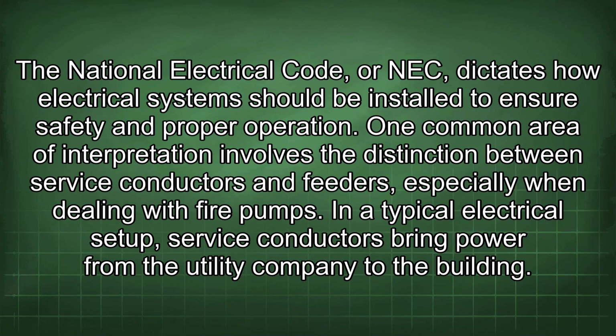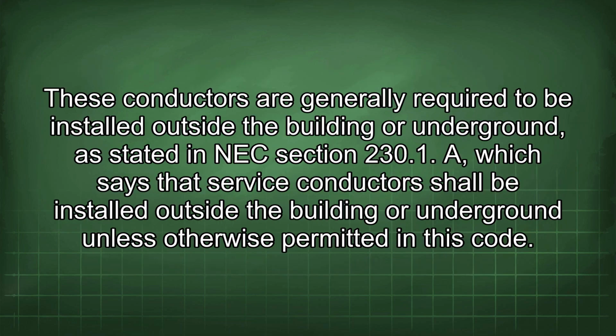The National Electrical Code, or NEC, dictates how electrical systems should be installed to ensure safety and proper operation. One common area of interpretation involves the distinction between service conductors and feeders, especially when dealing with fire pumps. In a typical electrical setup, service conductors bring power from the utility company to the building. These conductors are generally required to be installed outside the building or underground, as stated in NEC section 230.1(A), which says that service conductors shall be installed outside the building or underground unless otherwise permitted in this code.